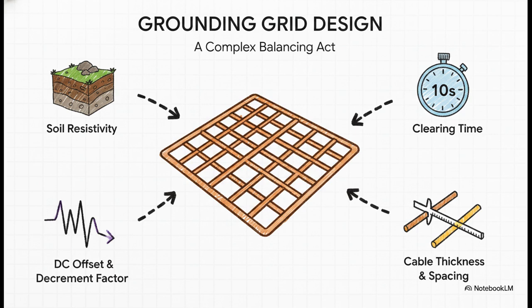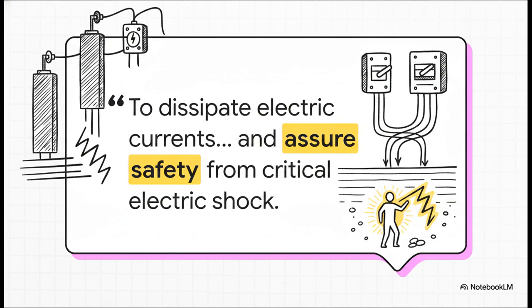Every single one of these variables dictates exactly how thick the buried copper cables need to be, and how closely together they must be spaced to flatten those voltage gradients at the surface. The ultimate goal, pulled directly from the IEEE standards, is simply this: to protect human life. All of this mind-boggling math, the towering switchgear, the high-speed differential relays, the precisely sized circuit breakers, and miles of buried copper, it all exists for one single purpose: to dissipate massive energy safely into the earth so that human beings are never exposed to critical electric shock.